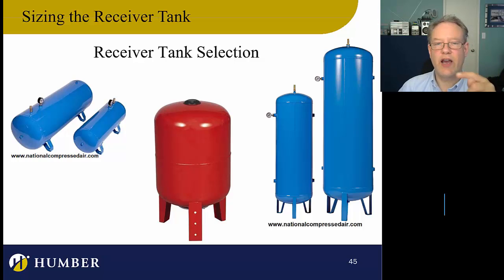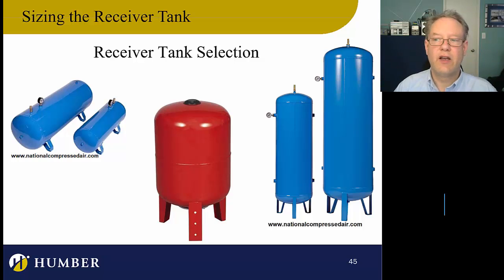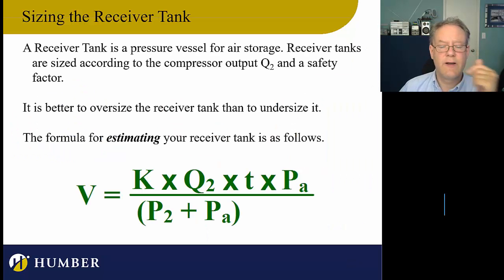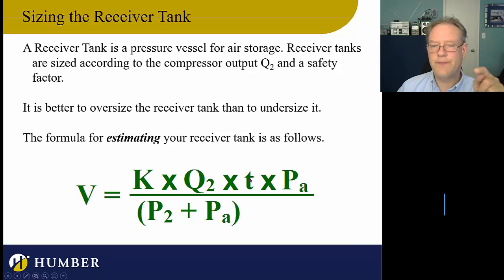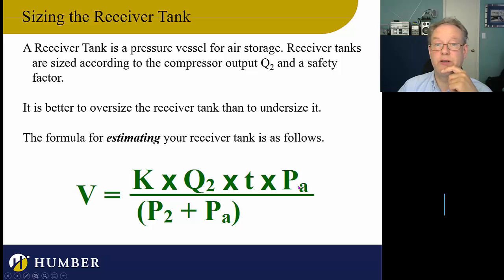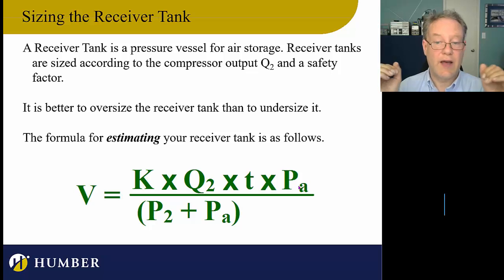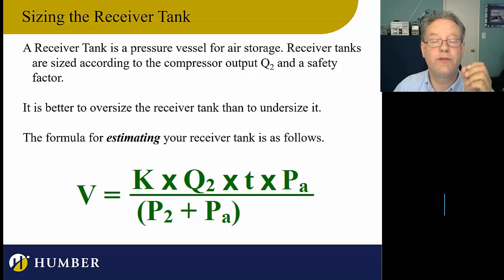Now about the receiver tank — you won't be doing calculations for receiver tanks in this course, but here's the concept. The formula includes K as a safety factor, flow rate out, time, and pressures. The receiver tank is like a capacitor in your system, allowing for fluctuations. The tank volume is dependent on atmospheric pressure, so if you're on a mountain or airplane, this formula gives a different number.